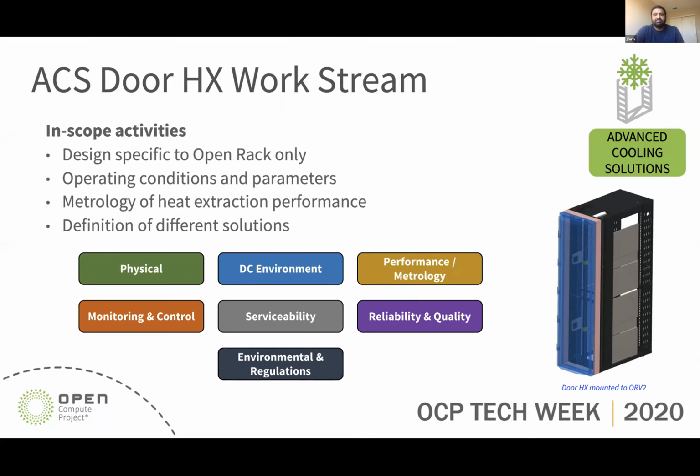One is design specific to an open rack only, looking at the data center environmental conditions and associated parameters, defining parameters of interest with regards to how to define performance of a door heat exchanger, and also associated specs or test conditions that could be used to evaluate the same, and the definition of different solutions or how a door heat exchanger solution could be employed in different ways. A lot of what's been summarized over here has been contributed as a document for IC review and been categorized into the following sections that are outlined at the bottom of the slide.